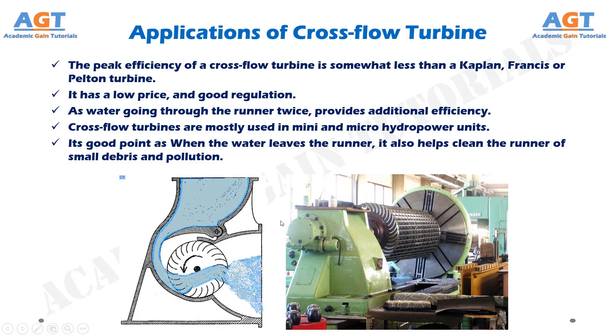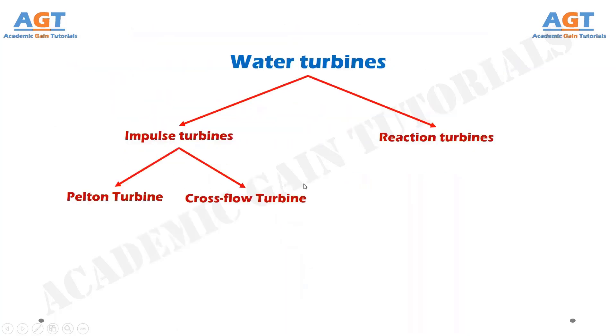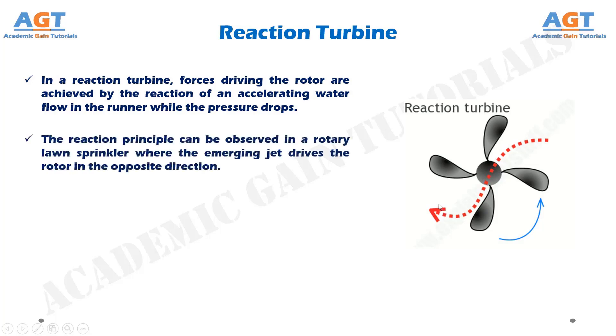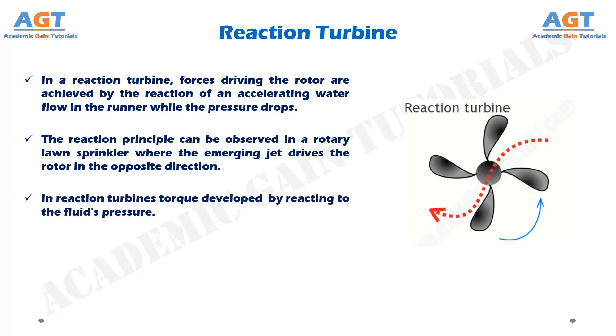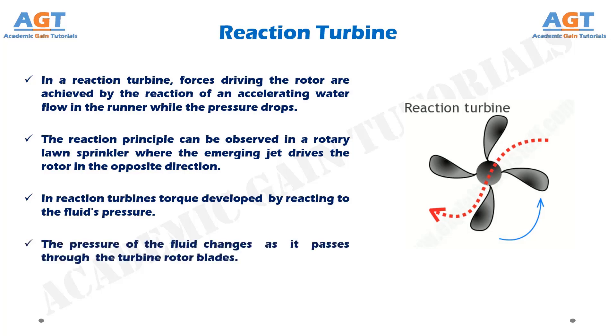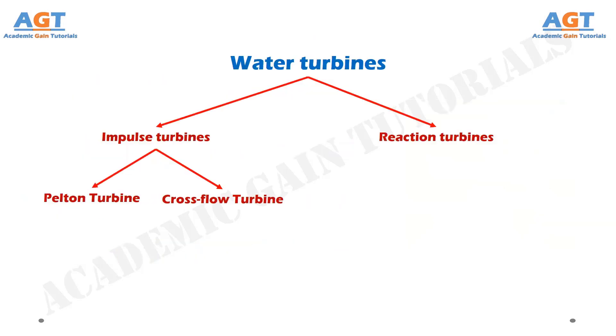We have studied the impulse turbines. Now let's look at reaction turbines. In a reaction turbine, the forces driving the rotor are achieved by the reaction of an accelerating water flow in the runner while the pressure drops. The reaction principle can be observed in a rotary lawn sprinkler where the emerging jet drives the rotor in the opposite direction. In reaction turbines, torque is developed by reacting to the fluid's pressure. The pressure of the fluid changes as it passes through the turbine rotor blades. The reaction turbines are of three types.